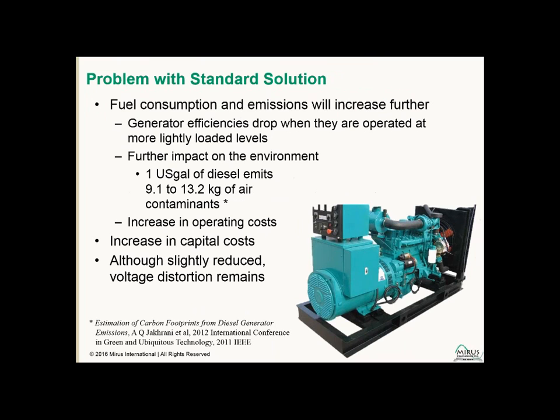So what's wrong with that standard and recommended solution? If we oversize, the generator is going to operate at much more lightly loaded conditions. When it runs at lightly loaded conditions, the generator's efficiency drops dramatically. A generator has optimal efficiency in around the 70% loading range. So as we lower that, the efficiency goes down, and with the efficiency going down, the fuel consumption goes up. As the fuel consumption goes up, as I mentioned earlier, we're going to emit more contaminants into the environment, and that can obviously cause problems with global warming and other issues related to environmental conditions. And we're going to increase our operating costs.